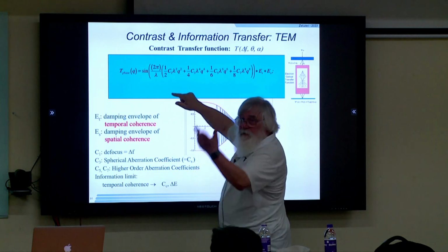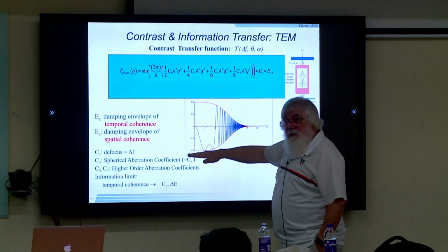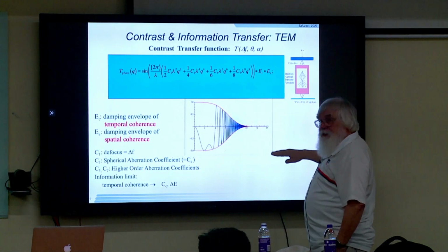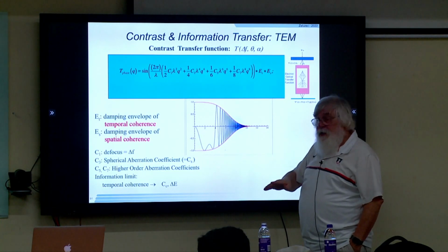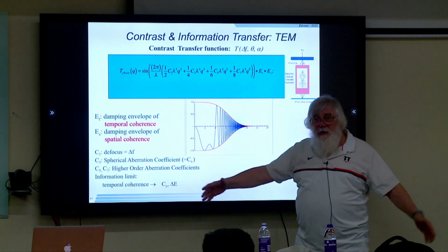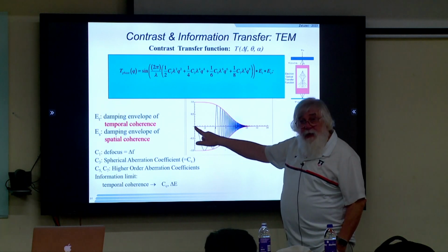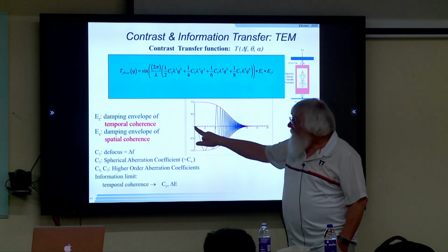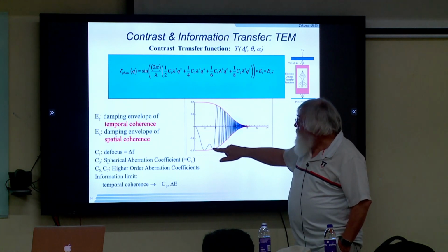Again, that should be alpha in the other curve. All right, so a perfect lens would have a perfect contrast transfer function. It'd be unity. In reality, it's never unity. For very low frequency, very large objects, an electron lens is pretty poor. It actually cuts off. The transfer is bad. Then there's a region where it's relatively high, and then it drops off again.